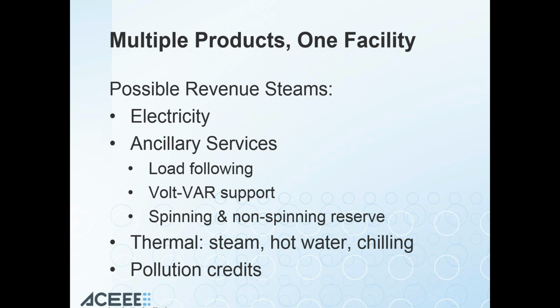There are multiple products coming out of one facility. We tend to think of just thermal load and electricity in kilowatt hours. Thermal could be steam or hot water, but people often forget you can also do chilling, using steam for that. On the electric side, you've got not just kilowatt hours but kW, and you can do load following services for the utility, spinning and non-spinning reserve, and volt-var or frequency control. There's a lot of different products out there that make this a better mousetrap.